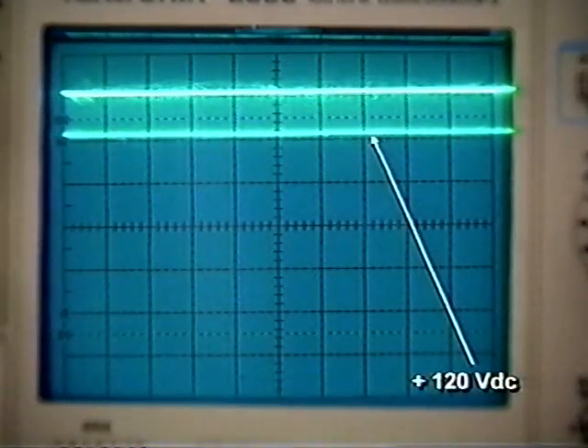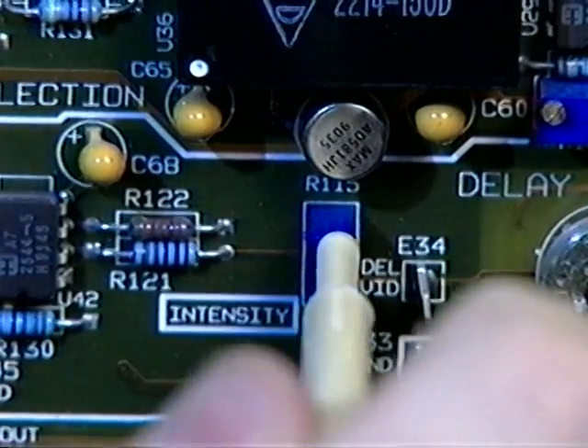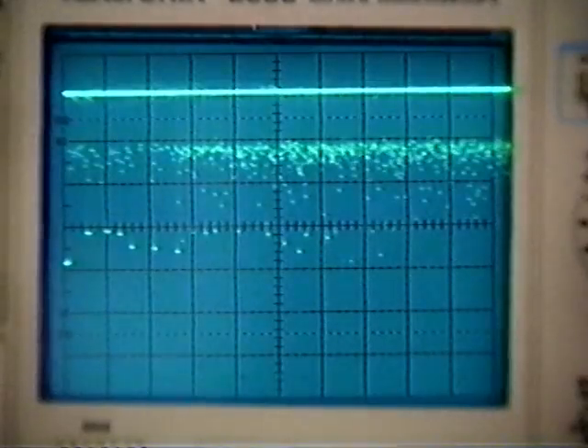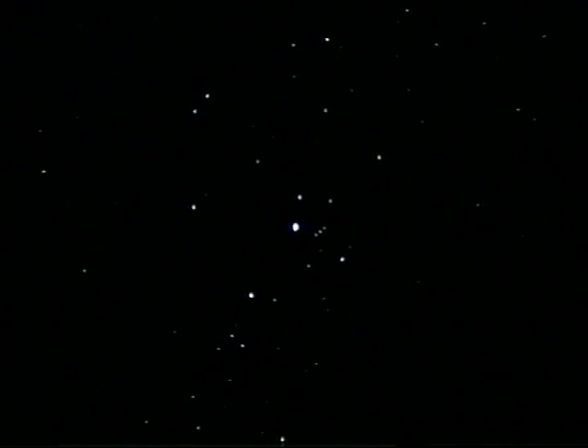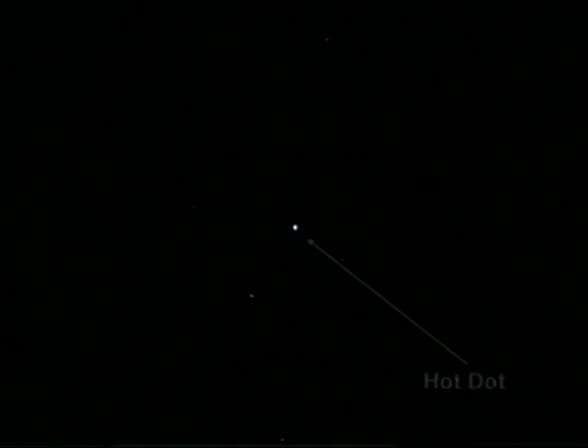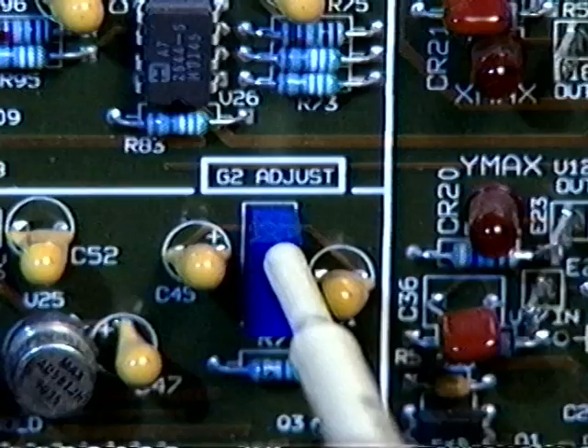Try setting threshold to somewhere between plus 115 volts DC and plus 125 volts DC. Reset the video level to plus 60 volts DC using the intensity control. Remove the oscilloscope probe and set G2 again, as described previously. Continue to increase the G2 level until stars are just visible on the dome. Do not adjust G2 so high that a hot dot appears on the center of the dome.